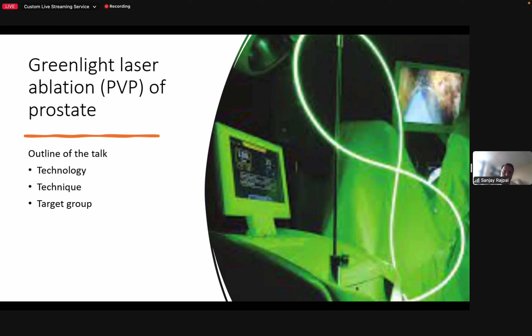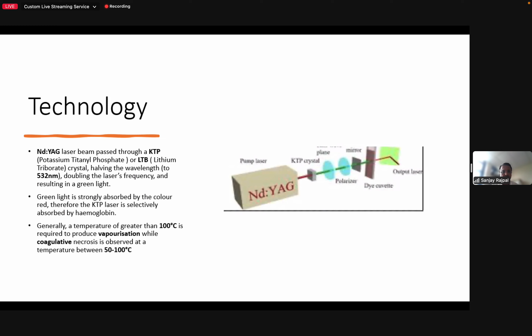It basically involves passing an Nd:YAG laser beam through a KTP or a lithium triborate crystal, which results in halving the wavelength and doubling the frequency. So the laser beam which comes out is in the visible spectrum, green in color, and measures 532 nanometers. This particular wavelength is important because it's strongly absorbed by oxyhemoglobin, and this is used for getting the therapeutic response. So there are two concepts resulting from this. When you have an energy source which raises the temperature of tissues to greater than 100 degrees centigrade, it causes vaporization. And when it runs between 50 and 100 degrees centigrade, you get a coagulative necrosis response.